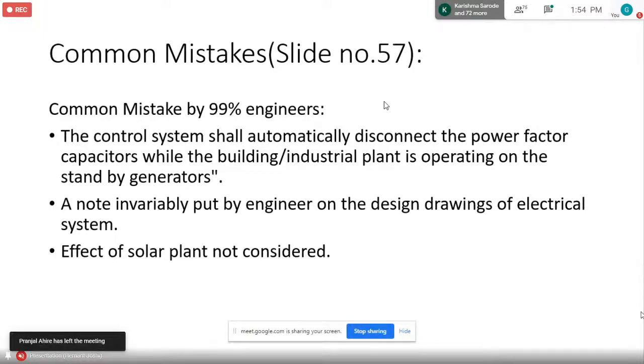No, it can. What happens is when the power goes off, all the capacitors drop out. The generator comes online, and then as the load is switched in, the capacitor bank starts switching in the capacitor units. So the generator is not seeing a leading power factor from the capacitor. The generator is seeing a good load power factor, operating at whatever the load power factor is, which will be about 0.96, 0.95. So what is the problem?